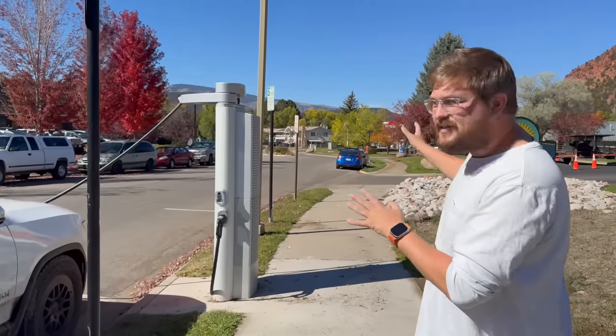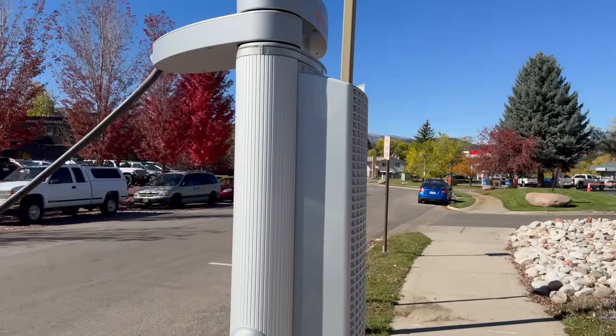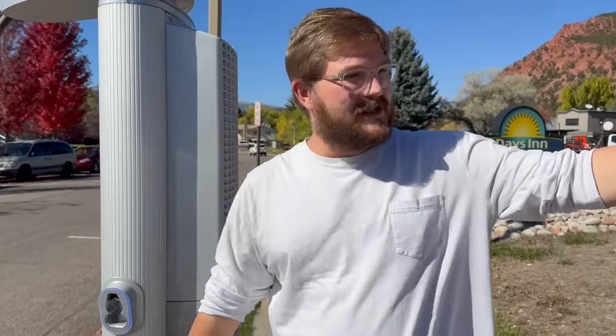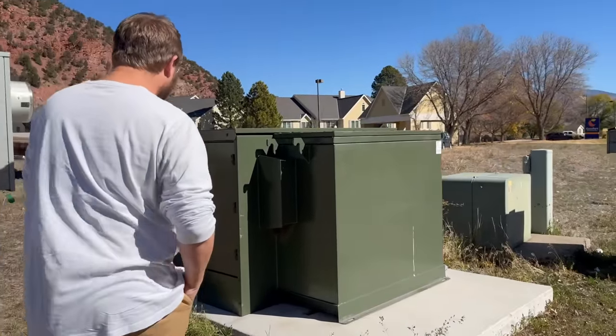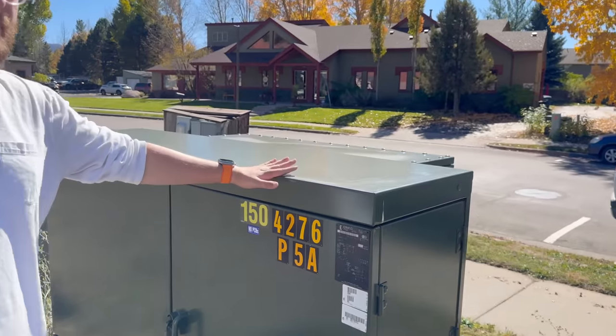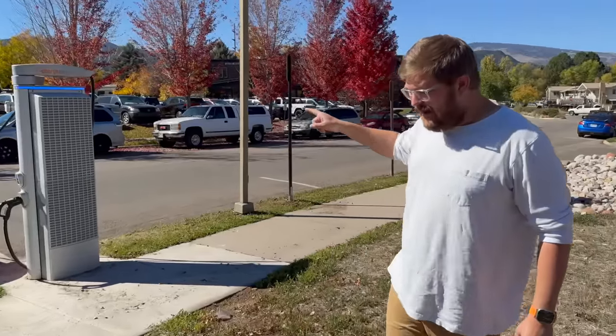These units are available in a few different configurations. This is what's called an all-in-one or a monolith, as ChargePoint would say. Basically the chargers and dispenser are all in the same unit — you can actually see the power electronics right here. We have a 150 kVA transformer at this particular site, roughly 150 kilowatts capable of power, hooked up to some switchgear which is then feeding this ChargePoint Express 250.